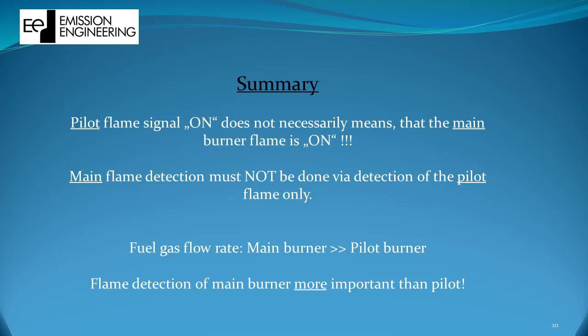Keep in mind, pilot burners often have heat releases in a range from 20 to 50 kW. Most refinery main burners have considerably higher heat releases. Even from that perspective, safety is more endangered the higher the flow rate. Without a dedicated flame detector for the main flame, a pilot flame detection cannot fully assist you.